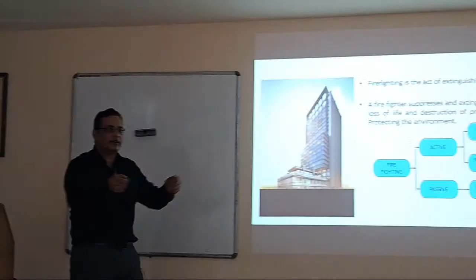Now passive - something very critical an architect may need to provide - is all the strategies for zoning, what we call fire compartments. When you do buildings of larger sizes, you have compartments which define zones - physical walling of compartments. For a basement car parking, it's 3,000 square meters per fire zone. Beyond that, you need one more fire zone. So it varies according to usage.